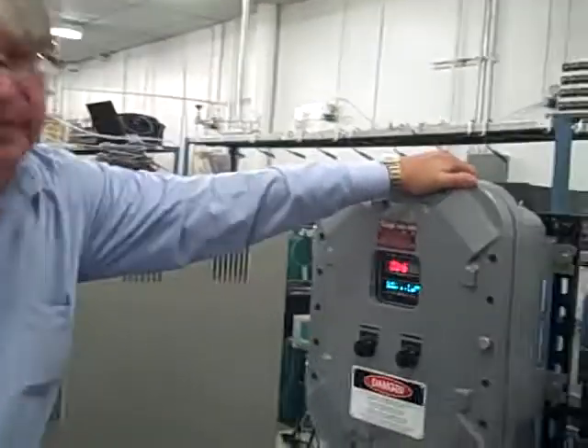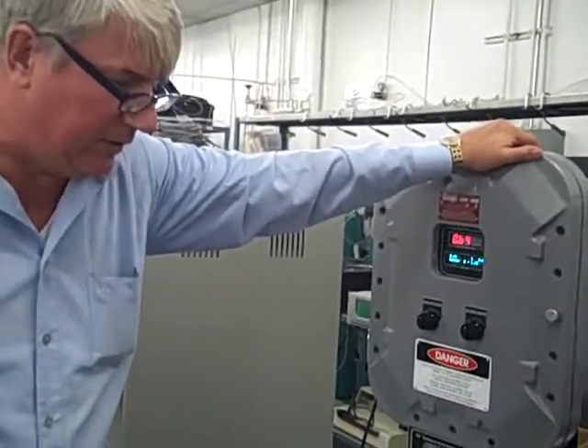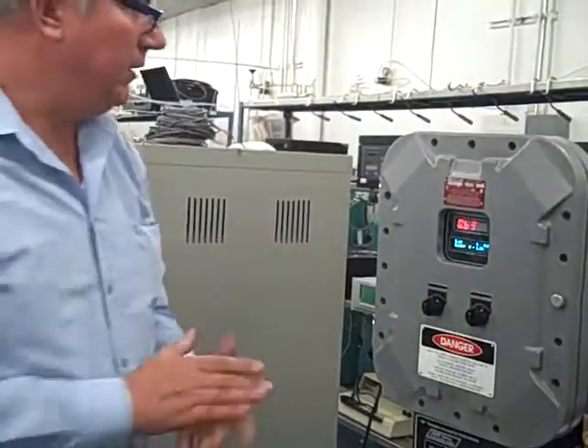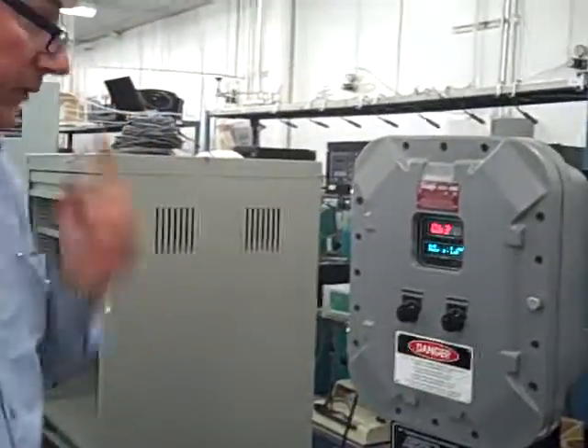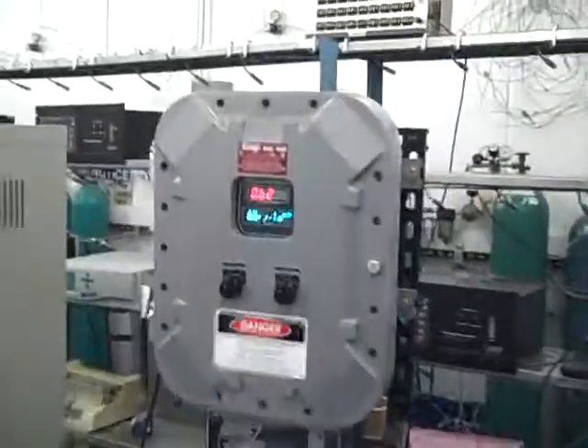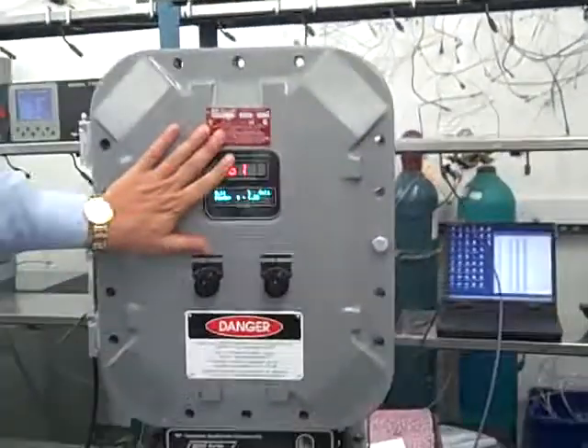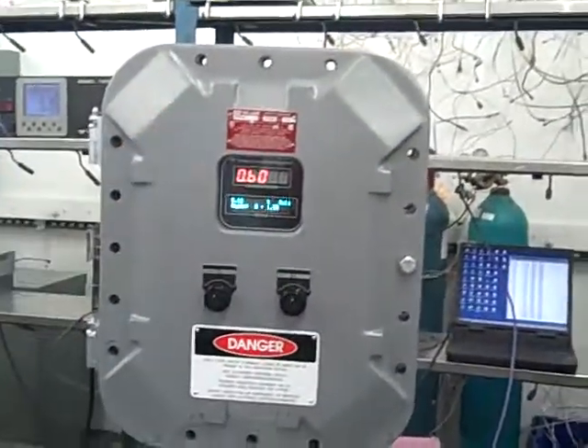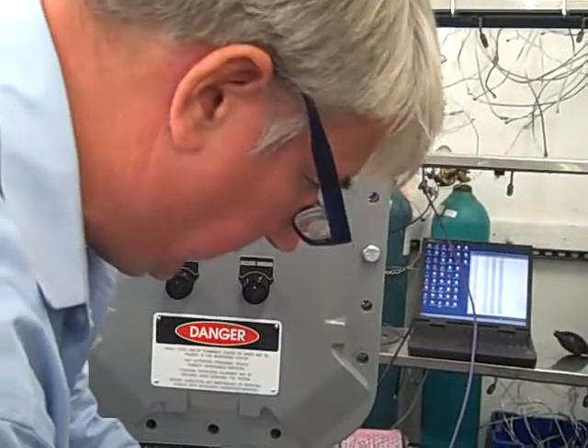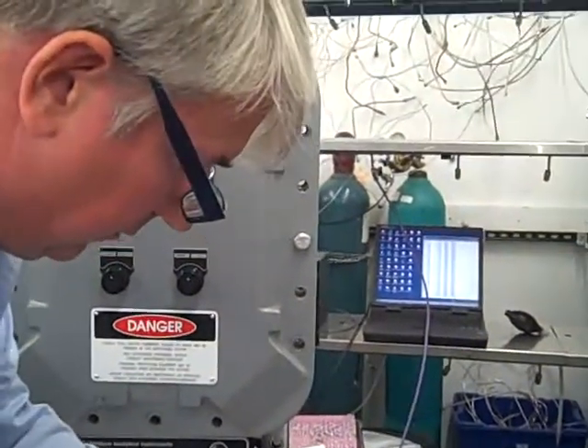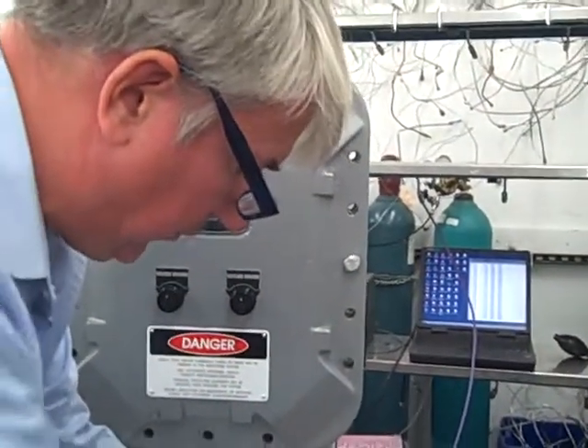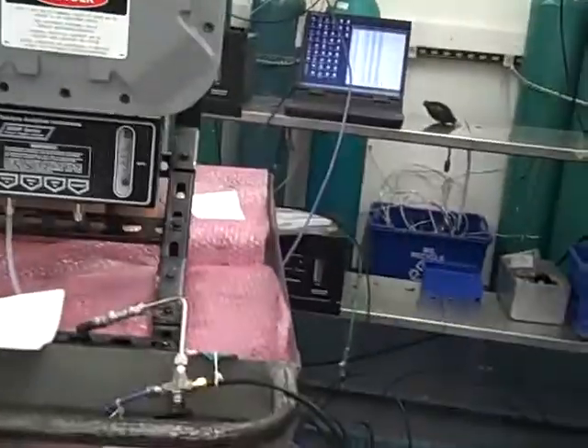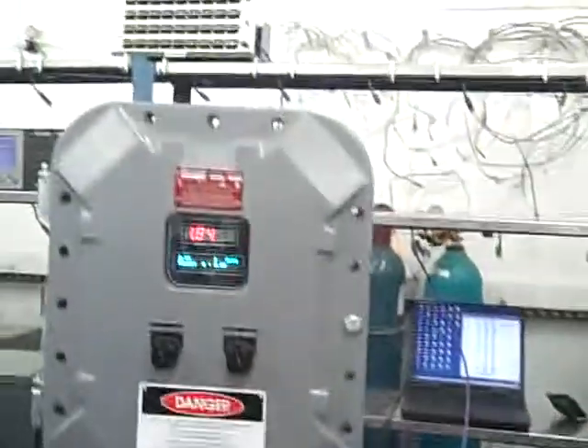If it's a percent analyzer like this, you can typically calibrate that within an hour of installation or less. And for a percent analyzer, which this is, it's very convenient to calibrate it on air. So right now we have the unit on nitrogen, as you can see. What we're going to do now briefly is switch this valve to put air in there. And you'll see it responds upscale very quickly.